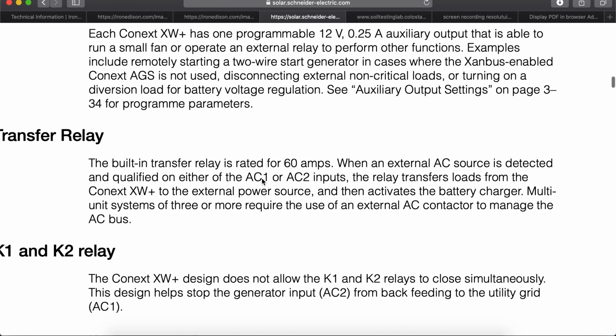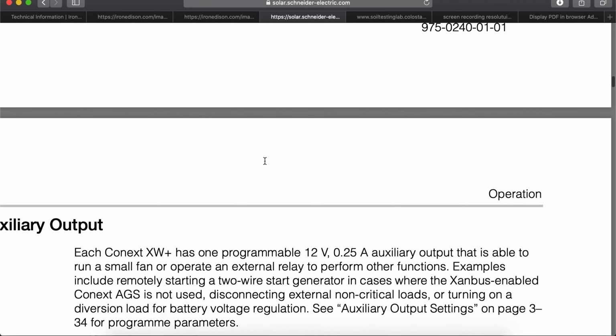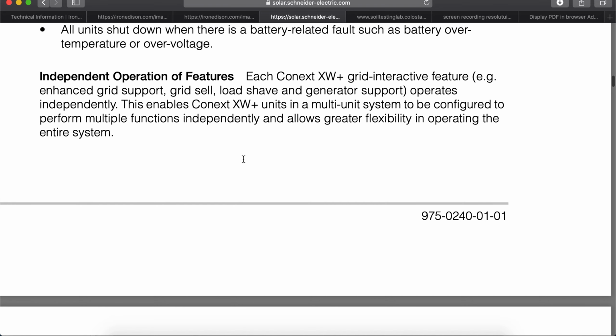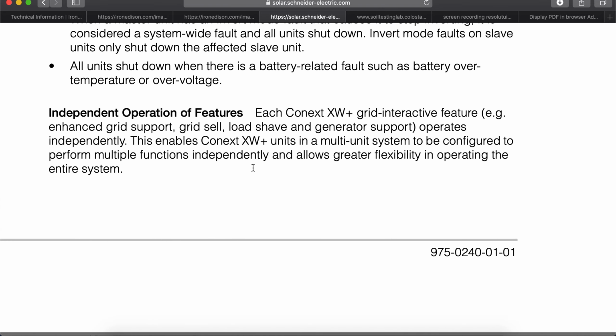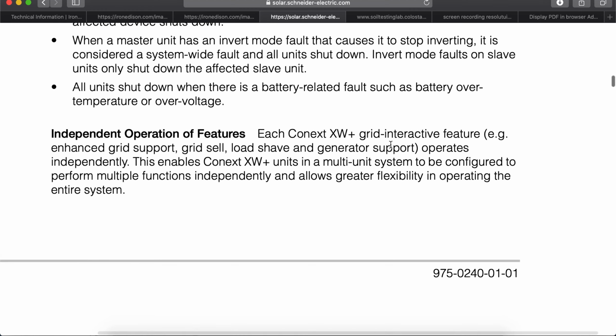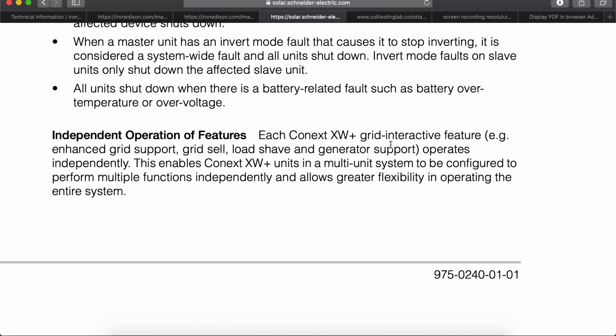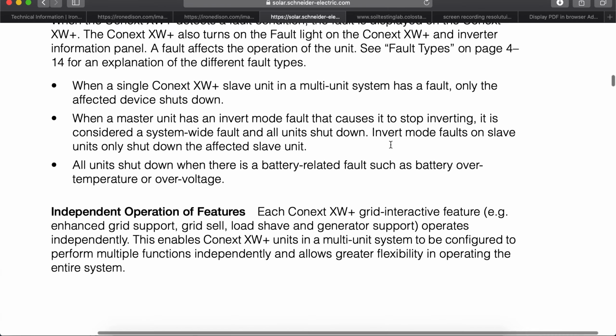Today I learned a couple of really important things that I didn't fully master yet. I thought this was an important note here, independent operation of features, telling me that each of the inverters can be configured independently. So even with the cascade setting enabled, we may find that some features aren't transferring over, and that's not the fault of the software. That's why it's important to read the manual and understand that each of the inverters in a multi-unit system would be programmed independently.